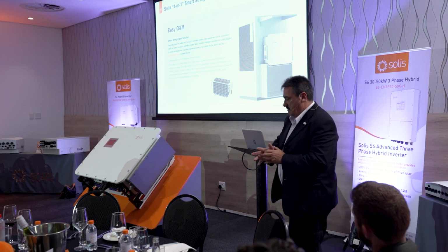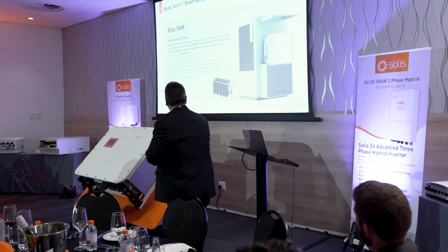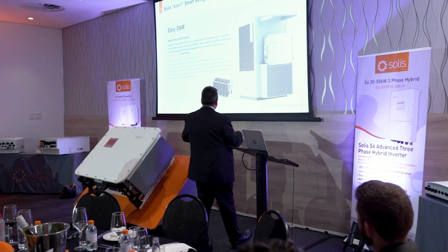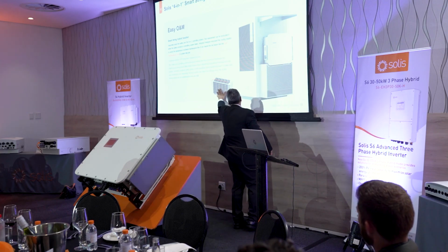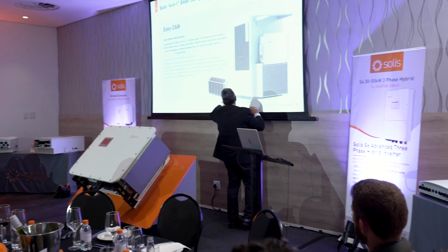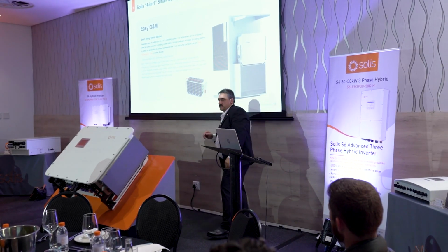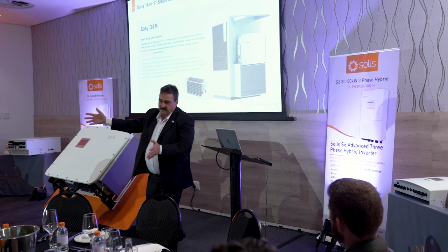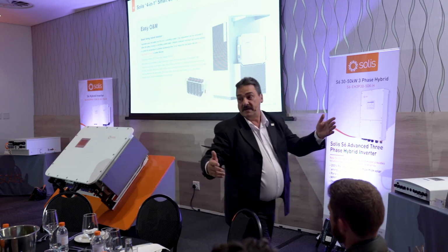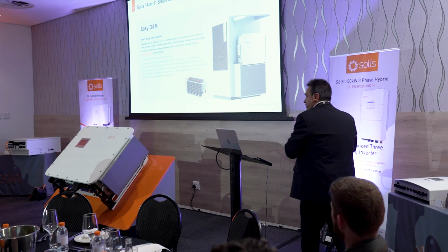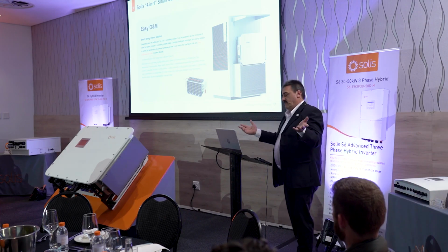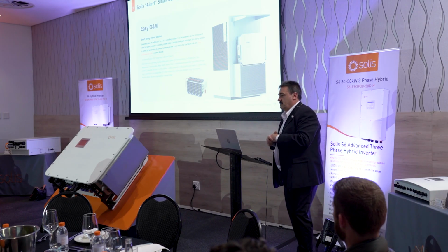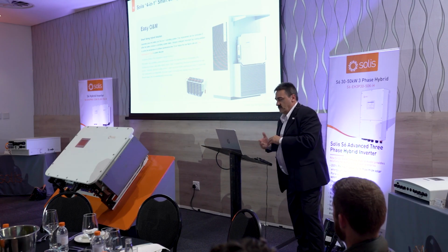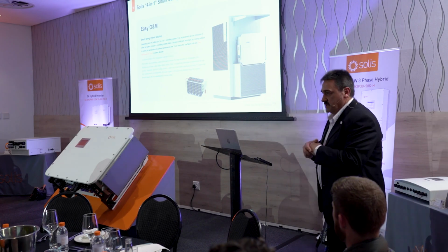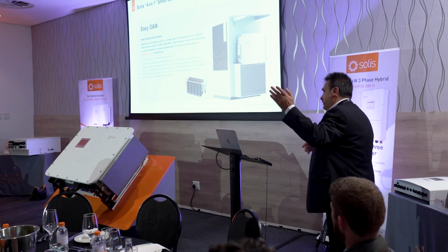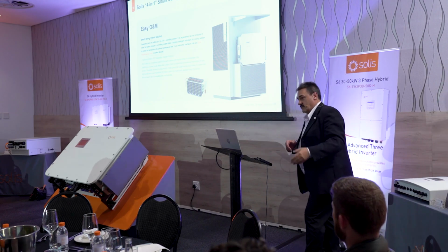So basically we call this a smart string hybrid solution, with separate battery placement in its own enclosure. We've separated this, because a lot of the time where there's a PCS in the system, the PCS and the batteries all live in the same container or enclosure space, generating even more heat within that enclosed space. And the more heat is in the space, the less efficient any system becomes. Batteries don't like too much heat, and they certainly don't like cold -- we all know that.